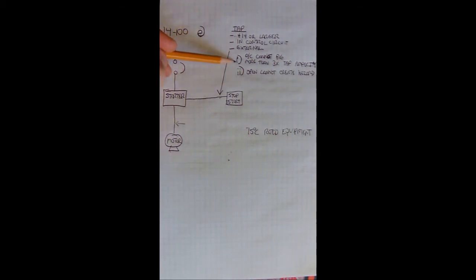Okay, and item I, we're going to move on, says the rating or setting of the branch circuit overcurrent device, this guy here, is not more than 300% of the ampacity of the control circuit conductor. So basically what we're saying is the overcurrent here, in this case the breaker, cannot be more than 3 times the ampacity of this conductor right here. That's what that rule says. And then II says opening up this circuit can't create a hazard, and that would just happen under normal conditions. We're not going to deal with a fire pump or anything weird. Okay, let's get started with some calculations.